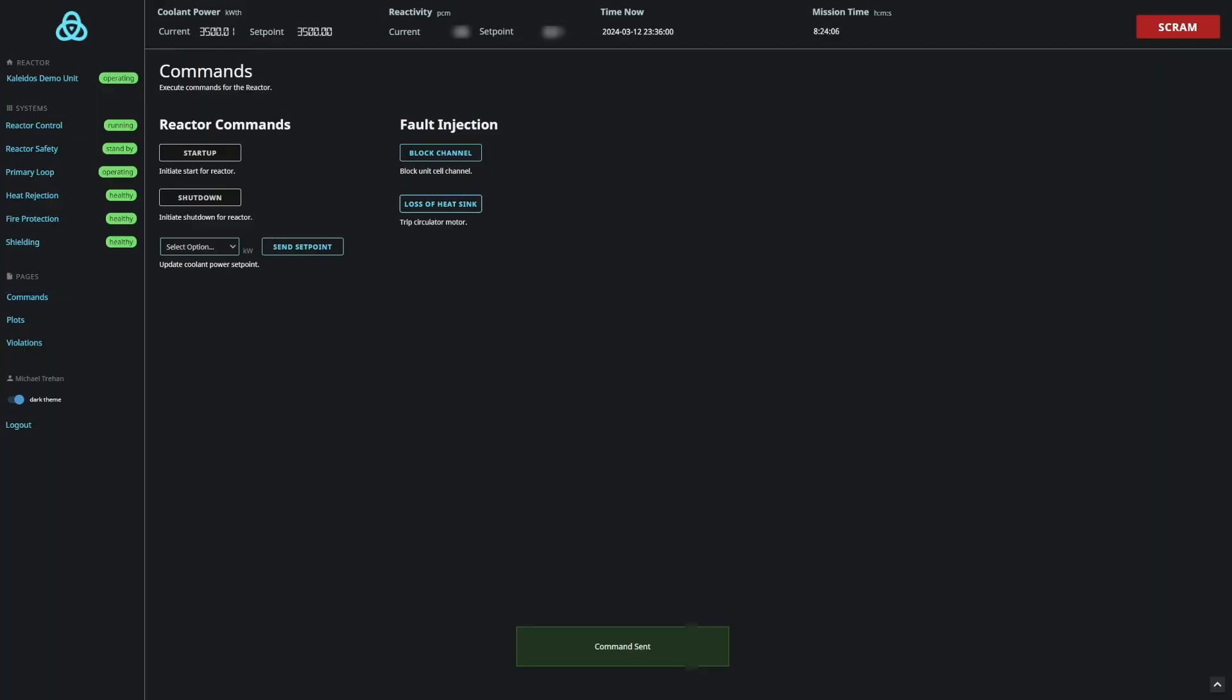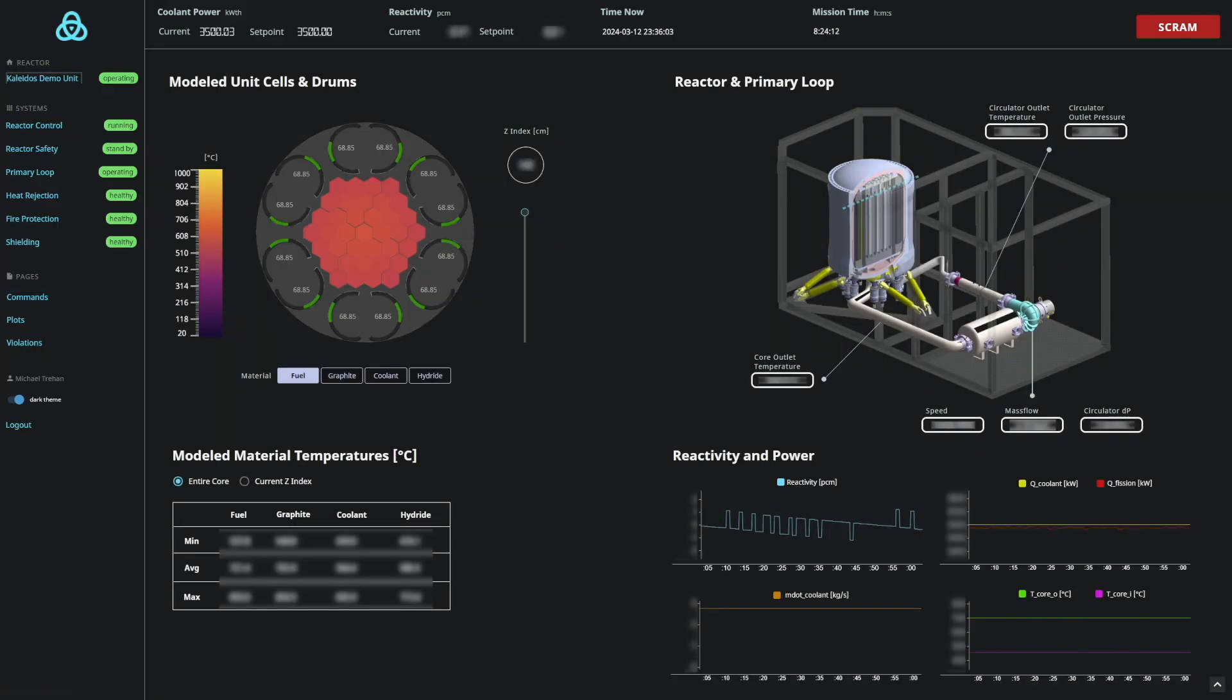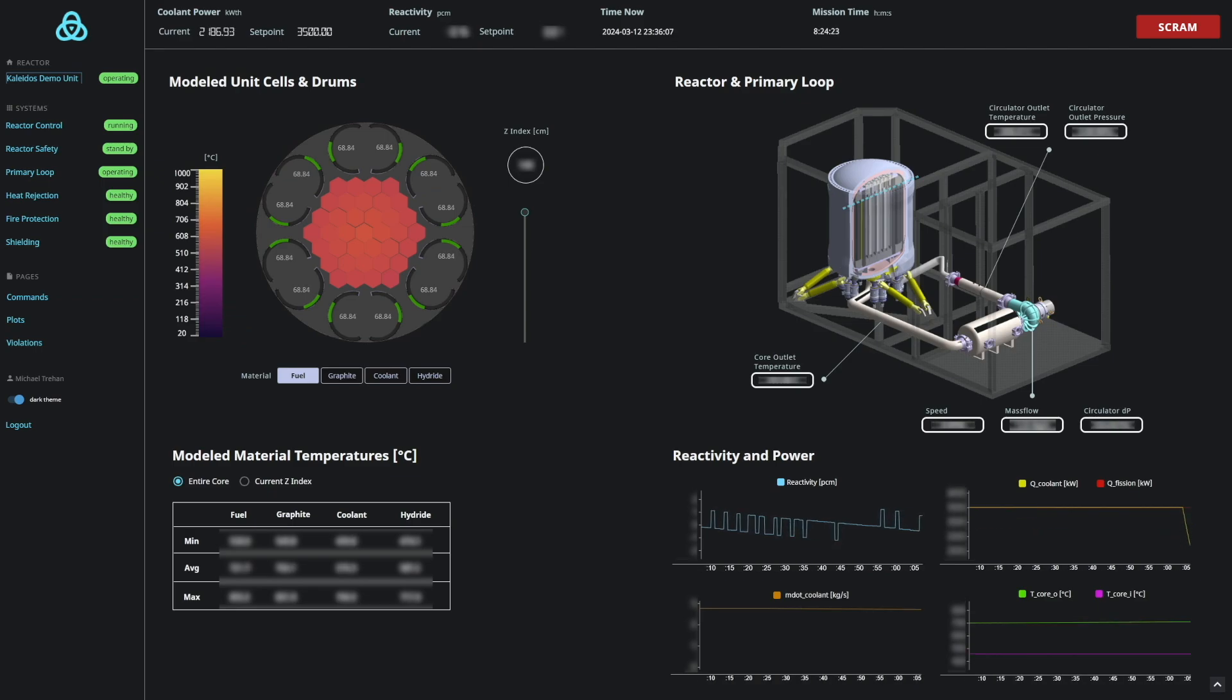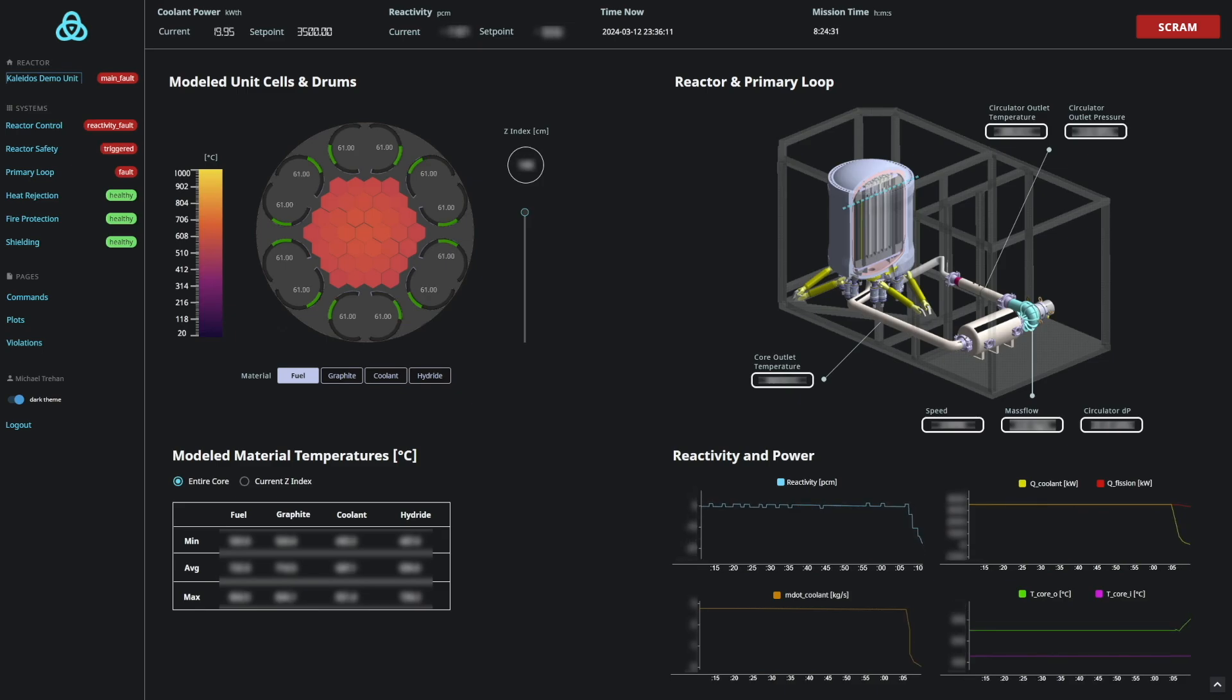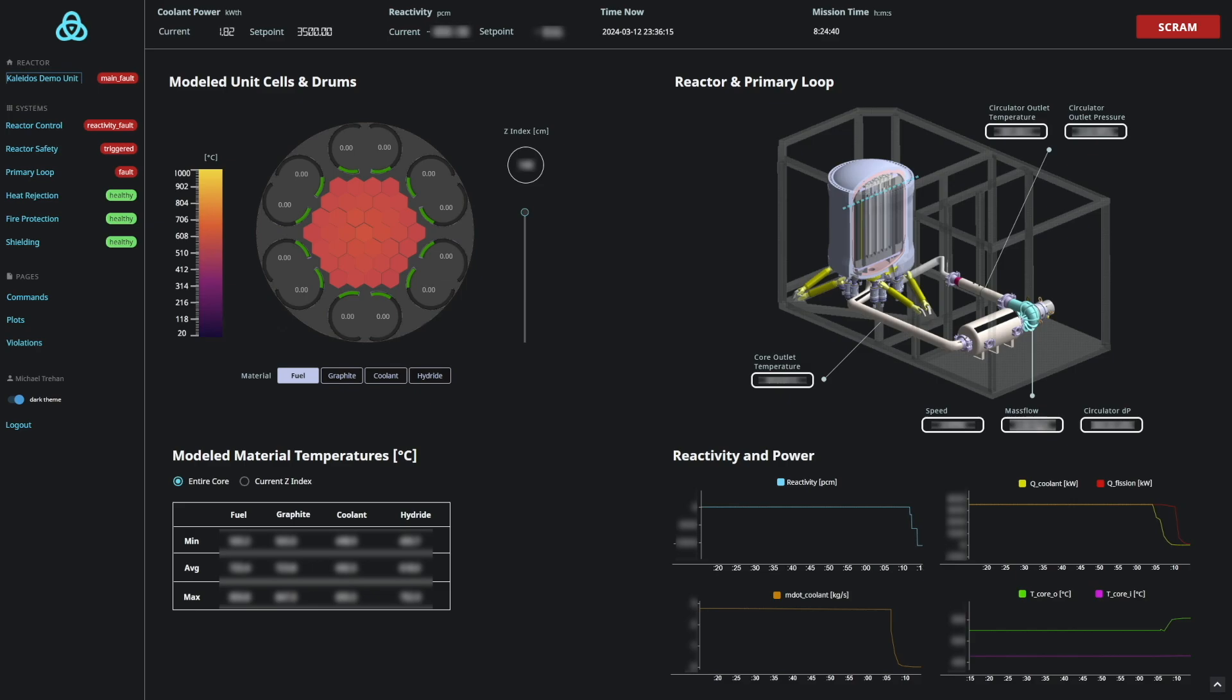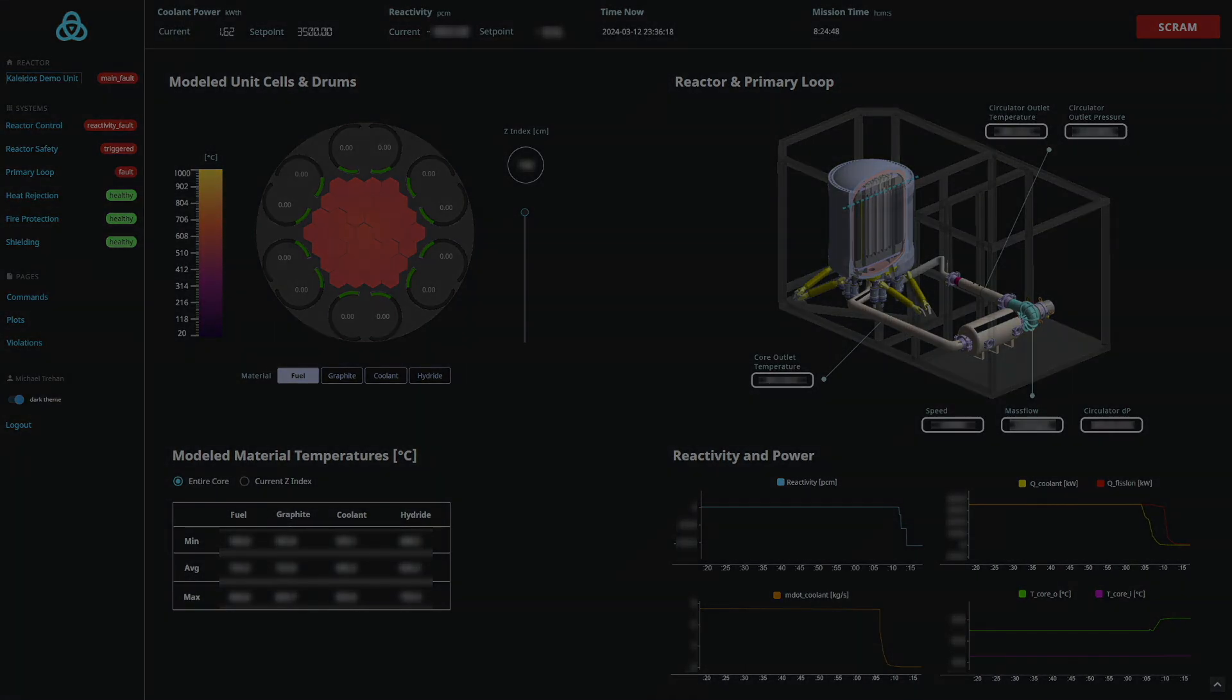Another scenario that we want to consider is the loss of our helium circulator motor. On initiation of this event, the mass flow rate drops to zero and temperatures immediately increase. In this simulation, the reactor safety system triggers a scram due to the increased temperature at the outlet of the core, and the control drums quickly rotate inward to shut down the reactor.